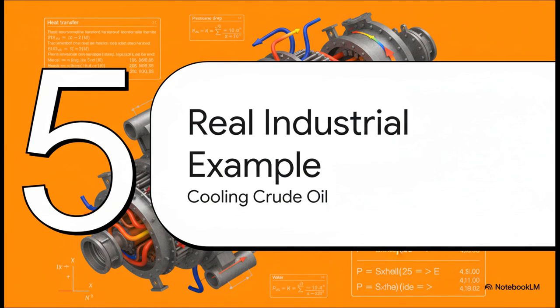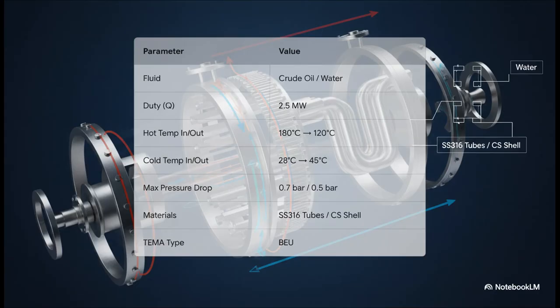All right, time to put all these pieces together. For our last section, we're going to walk through a complete design for a classic refinery application: cooling down hot crude oil with cooling water. So, here are our design parameters. We need to cool crude oil from 180 degrees Celsius down to 120. We're using cooling water that's going to heat up from 28 to 45 Celsius. We've got really strict limits on our pressure drop, and we've picked stainless steel tubes to handle corrosion. And just like we discussed earlier, a BEU type is a really good fit for this job.